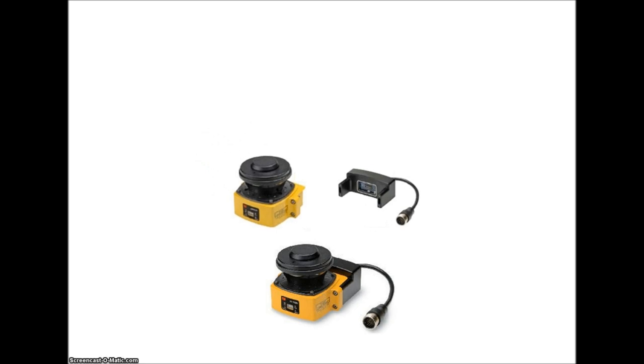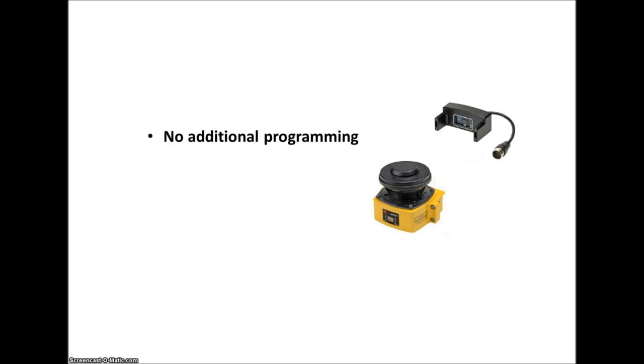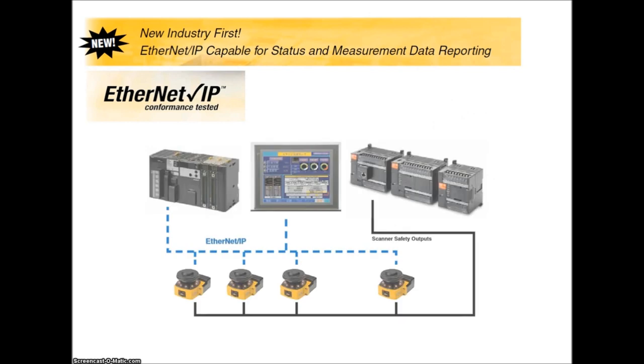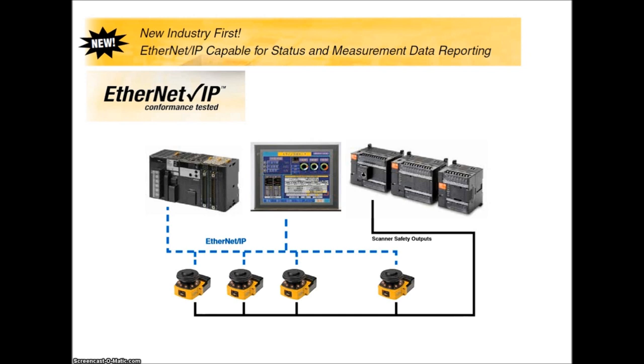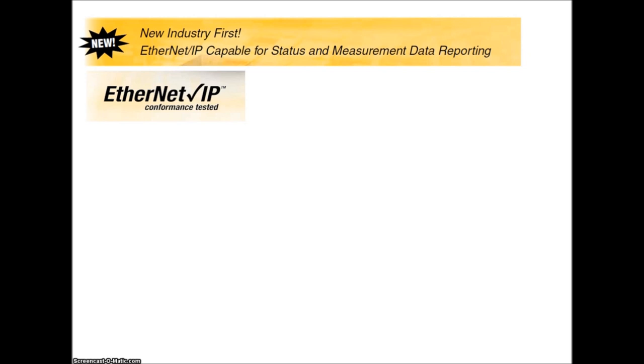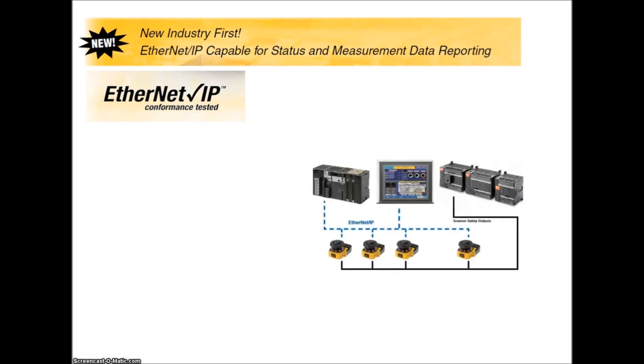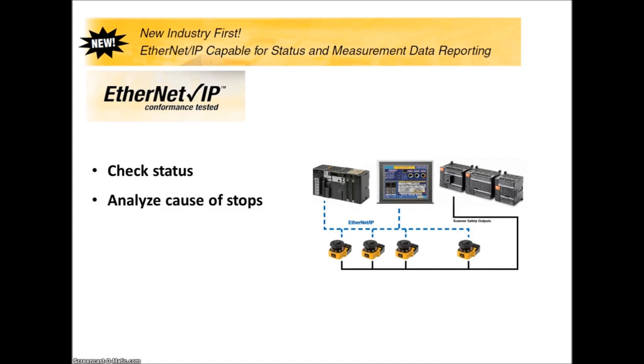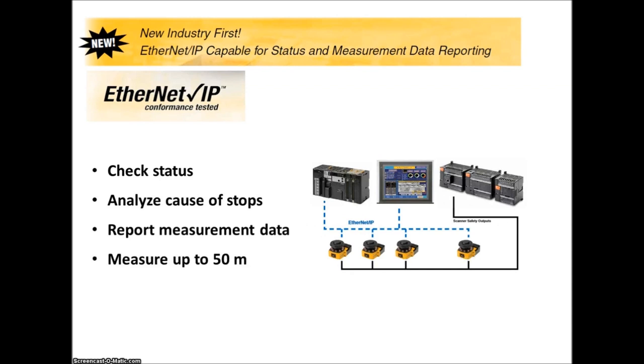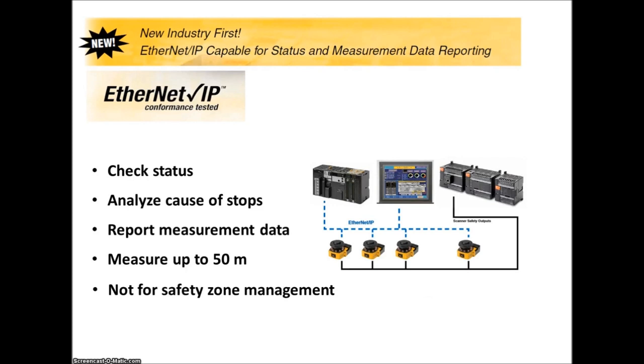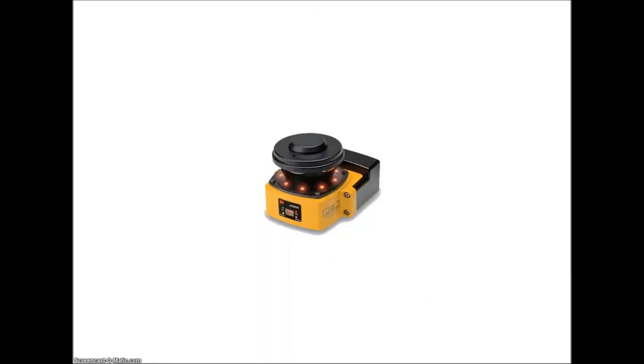And you get to keep all of your previously stored data without ever having to reconnect your computer. The newest feature of the OS32C and as a first in its industry is data management over Ethernet IP. You can now manage multiple units over a local area network. The Ethernet IP protocol allows you to check status, analyze the cause of an emergency stop, and report measurement data. Measurement data ranges up to 50 meters, which is much longer than the safety rated value. Remember that the Ethernet IP protocol is for data passing only and is not involved with the safety portion of the unit.